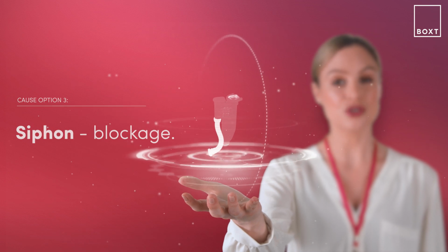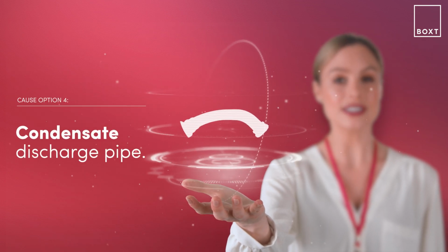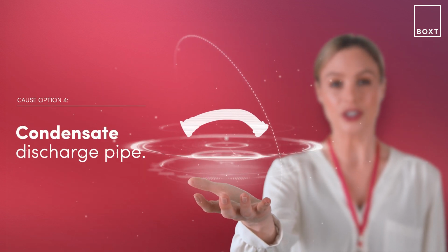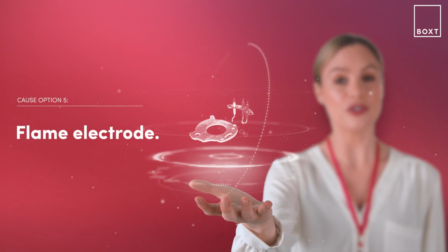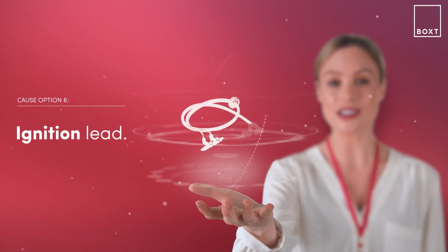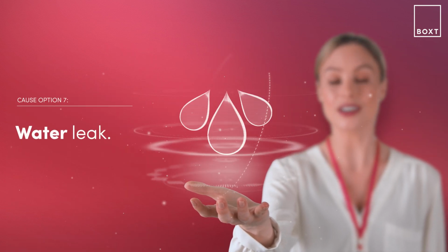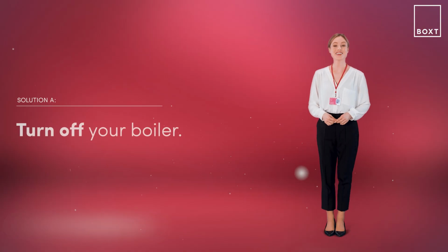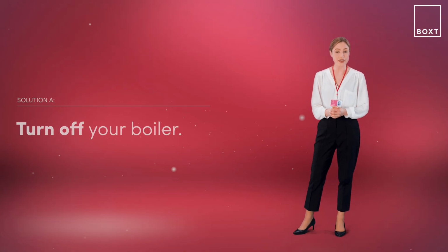If temperatures are extremely low, it could be that your condensate discharge pipe is frozen. The fault could also indicate damage to the flame electrode, the ignition leads, or possibly a water leak inside your boiler unit. First, let's start by turning your boiler off at the mains.